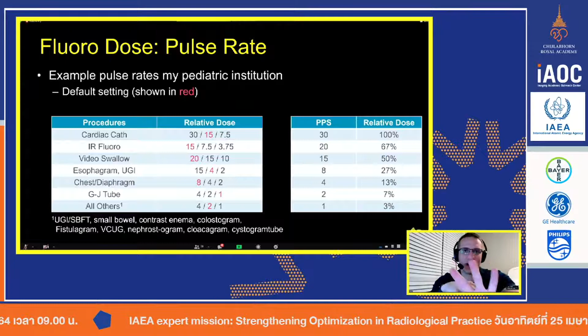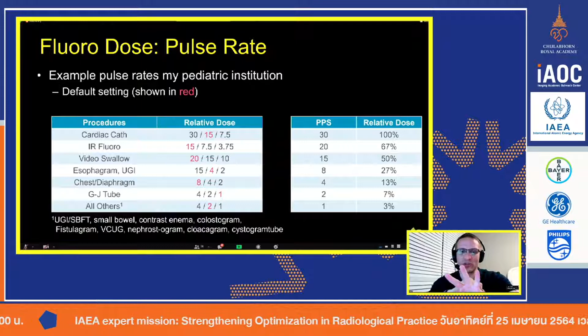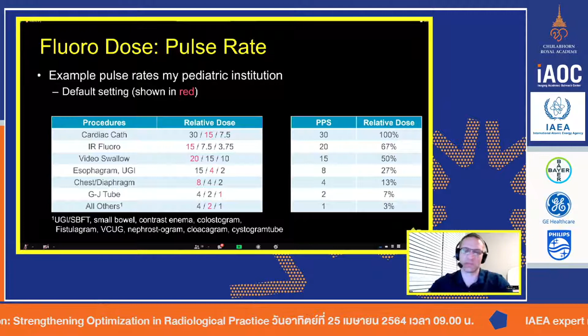So if the radiologist goes in there and they're trying to place this GJ tube and they're running into a little bit of problems, maybe they'll choose to go up to 2 pulses per second, or even maybe 4 pulses per second. So all they have to do is push the next button up or the next button up. Now they have no choice. They can't go up to 8 or 20 or 15 because that's just not an option in that protocol. So there is a limitation.